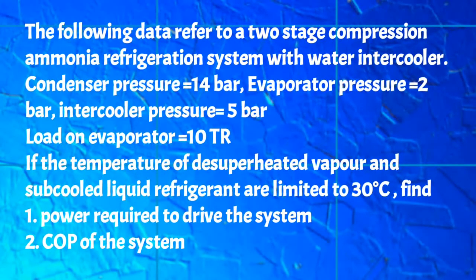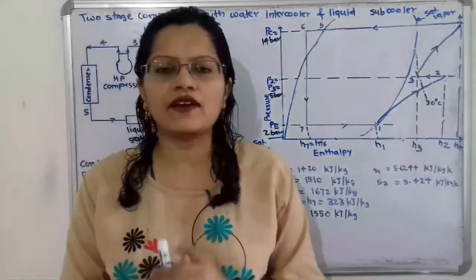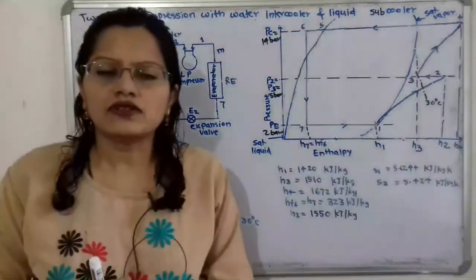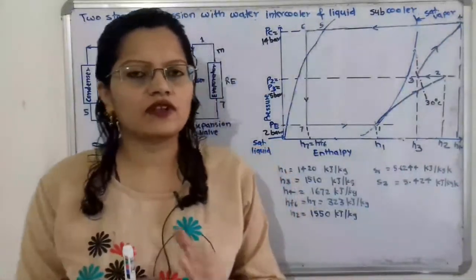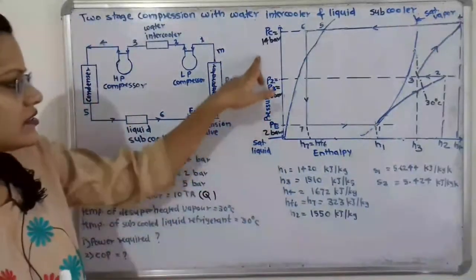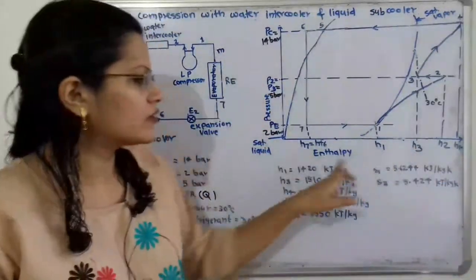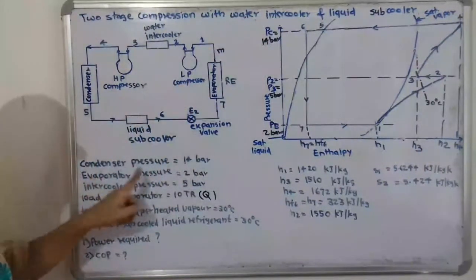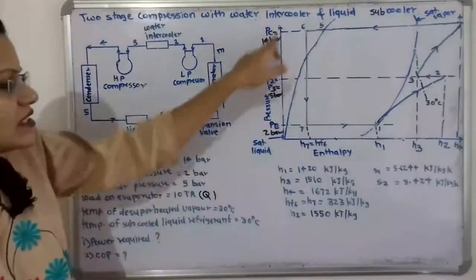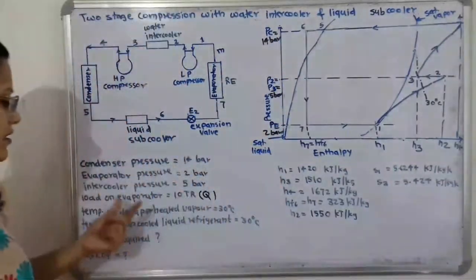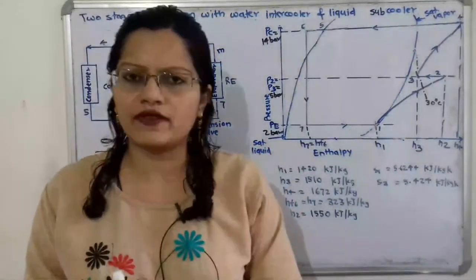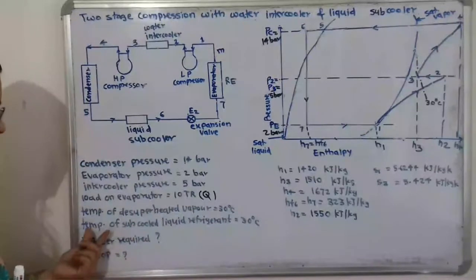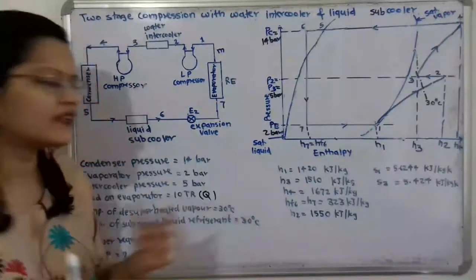We have to find the power required to drive the system and the coefficient of performance. In the exam, the pressure-enthalpy chart for ammonia refrigerant is provided — on the vertical axis is pressure and on the horizontal axis is enthalpy. We select three pressure lines: condenser pressure 14 bar, evaporator pressure 2 bar, and intercooler pressure 5 bar. The load on the evaporator is 10 tons of refrigeration, denoted Q. The temperature of desuperheated vapor and subcooled liquid refrigerant is 30 degree Celsius.